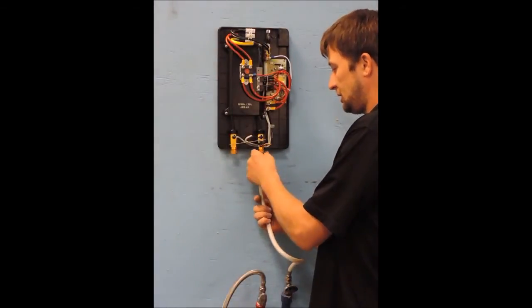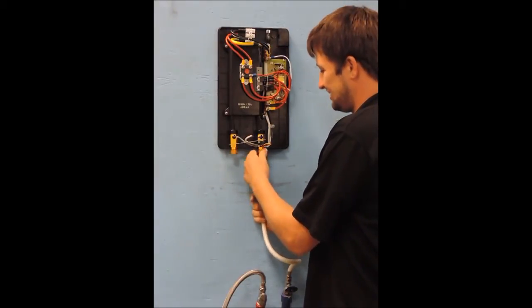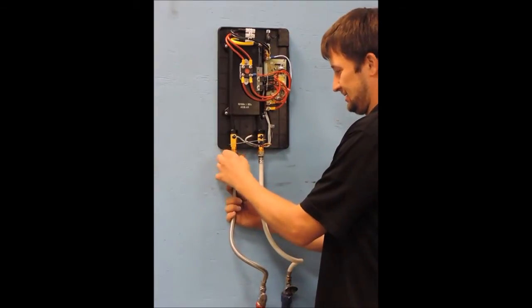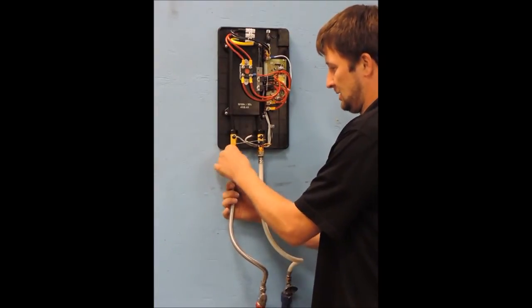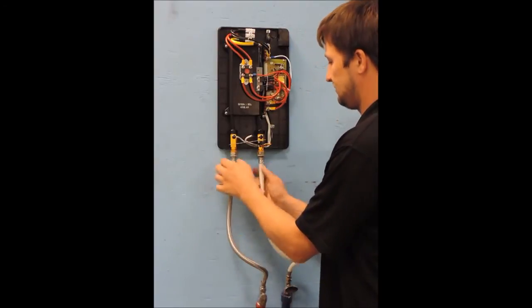We are now ready to make our plumbing connections. We use one half inch NPT for both the inlet and the outlet fittings, which can be found on the bottom of the unit. The cold water inlet is on the right hand side, and it should be preceded by a high pressure discharge valve and a shut off valve in that order.